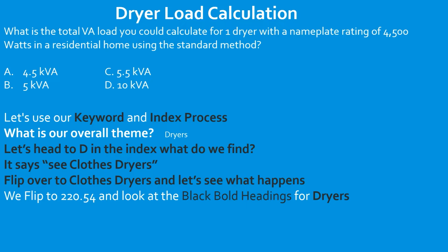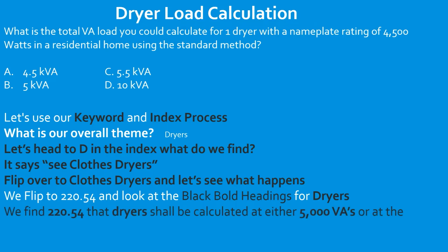It says loads for household electric dryers shall be either 5,000 watts or the nameplate rating. Okay, so it's either 5,000 watts as a minimum or the nameplate rating if it's larger than 5,000 watts. We're going to do a million of these questions, so don't feel like you have to fully understand that right now. But the code is stating that at a minimum, if you have a clothes dryer, you're required to calculate it for your load calc at 5,000 watts. But if it's larger than 5,000, then we're going to calculate it at whatever the nameplate is. So we're going to do it at 5,000 VAs, or the nameplate, whichever one is larger.